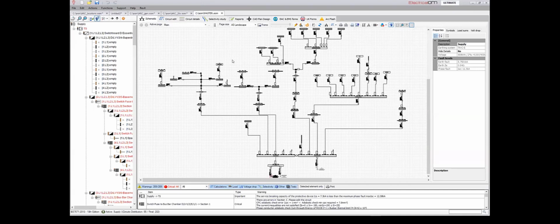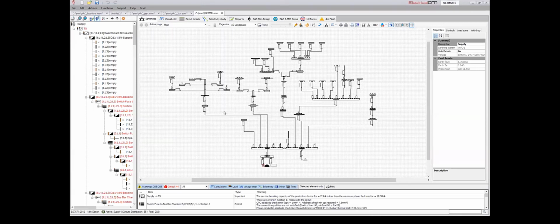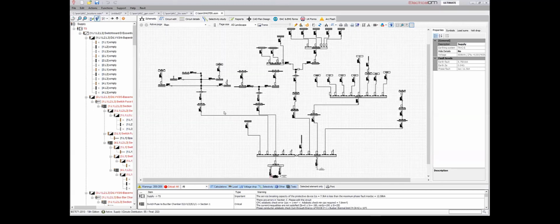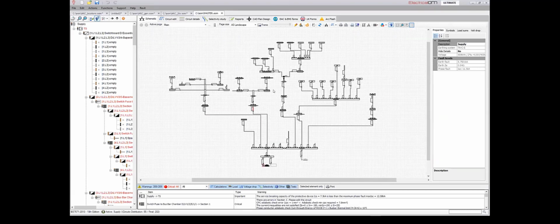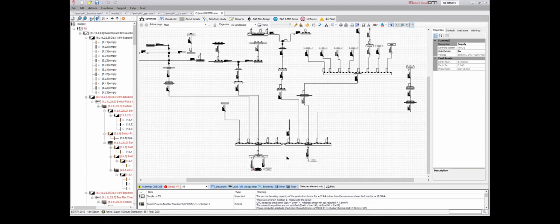Now I will show you how you can perform arc flash studies on an existing system, which is the common case. So as I said, we need to create a single line diagram, and then of course define all the necessary information like devices and cables, size, the equipment, and so on. But you may have a case where you're inspecting an existing installation and you have been told to carry also arc flash study assessments for the panels in this network. So you may end up having something like that, which is a complete design.